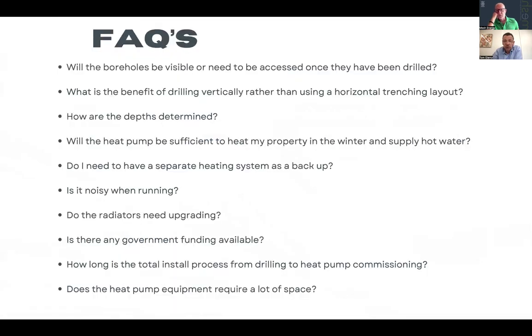Mm. And then what's a typical installation cost for a borehole? So how does that work? I mean, we know roughly how much an air source heat pump costs. A ground source heat pump will be almost twice the price of the air source heat pump. Maybe not exactly, but the drilling part is quite expensive, because you've got the drilling, you've got to do header works, and you need to then do the trenching to connect the boreholes together.